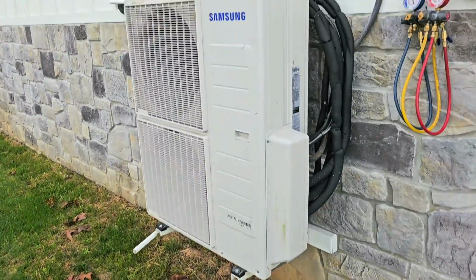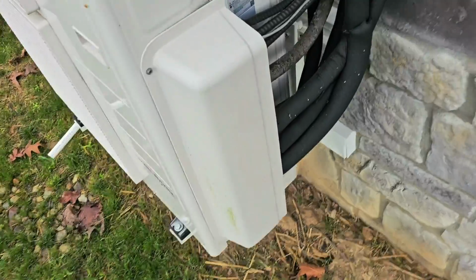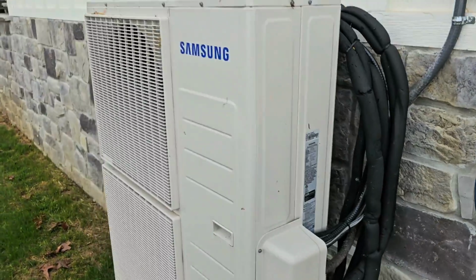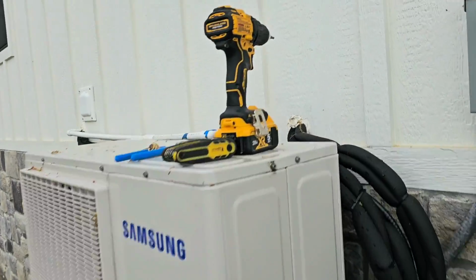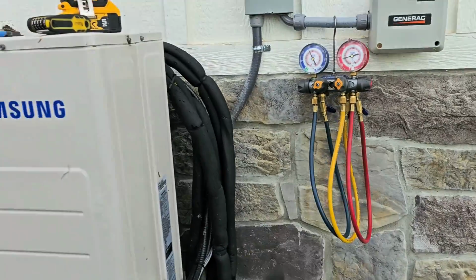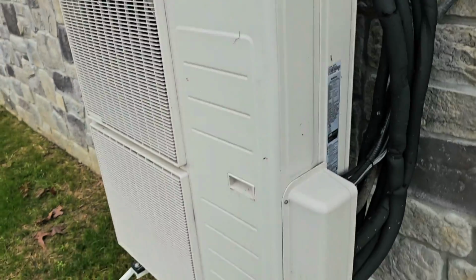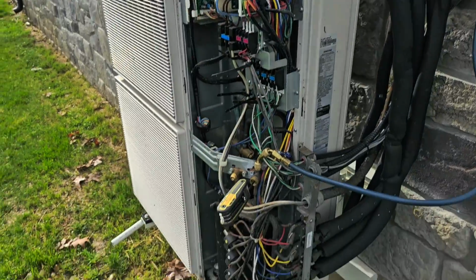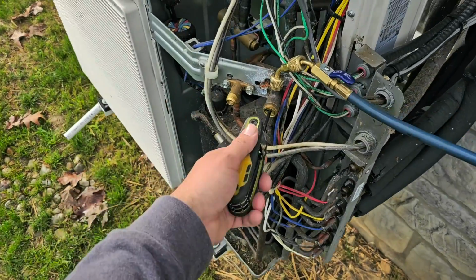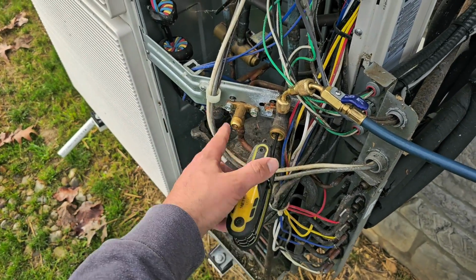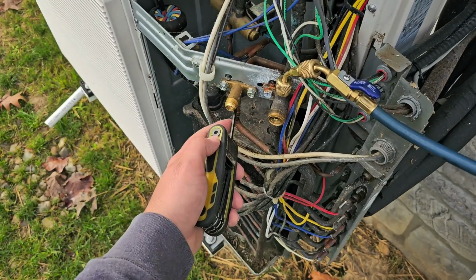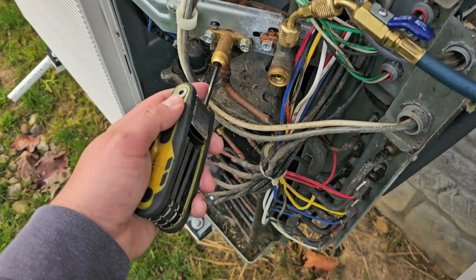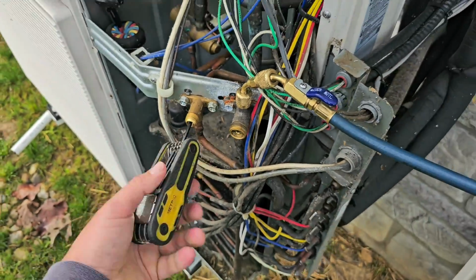All right, let's go. Here's the outdoor unit, and we've got 3 indoor units, so we've got 3 sets of piping. I'm gonna go ahead and take the Phillips bit that I've got in the cordless drill, take this panel off, attach the gauges, and start pumping the equipment down. Now I'm ready to perform the pump down. I've got the Allen tool ready to close the suction line and the liquid line service valve. Before we start the pump down, we're going to close the liquid line service valve using the Allen tool.